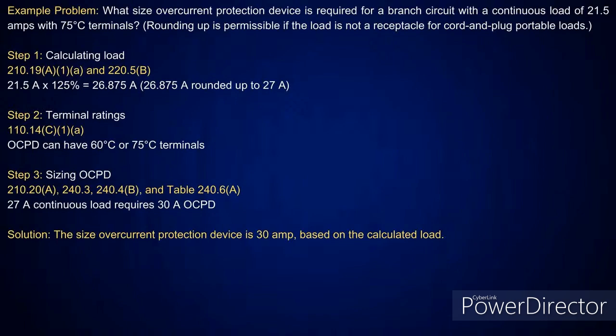I like how you put that 110.14(C)(1) in there, because if you don't know the terminal rating, then you have to go up to the 60 degree C column. That's correct. And that's why in the problem up there, we tell you 75 degree C column. So if I was sizing the conductor here, it would be a number 10. But it could be different if it was 60 degree C terminals. That's why in the problem we told you 75 degrees C, just to kick everything off.